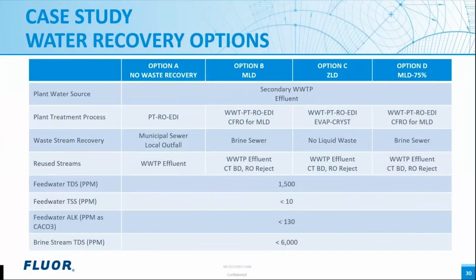Option B is minimum liquid discharge. It recovers 95% of the cooling tower blowdown and the RO reject and leaves a 5% brine stream, which is disposed to a brine sewer. Option C is zero liquid discharge, ZLD, and it recovers all the brine and disposes solids to a landfill.